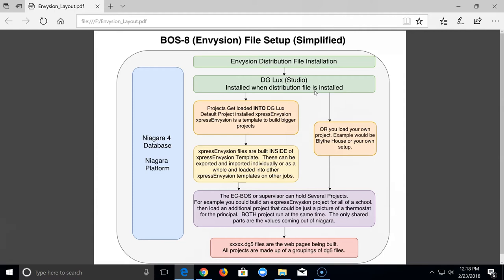If you're not using xpressEnvysion and just putting your own thing on it, there's not another project inside the project — you're just making one piece. Originally DG Lux was built with no xpressEnvysion, and it's hard software — really powerful but takes a lot of training. So what they did was make a project to simplify it with drag-and-drop equipment graphics. That's what xpressEnvysion was built for, also called Project Assist or PA. You'll see folders called PA — that's Project Assist, the DG Lux branded name for the same thing.